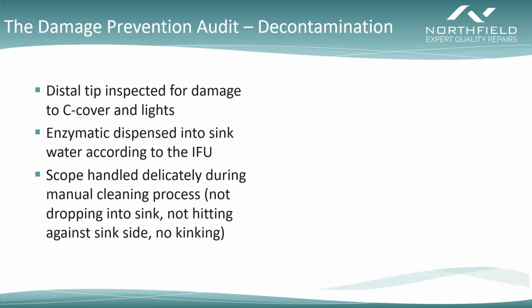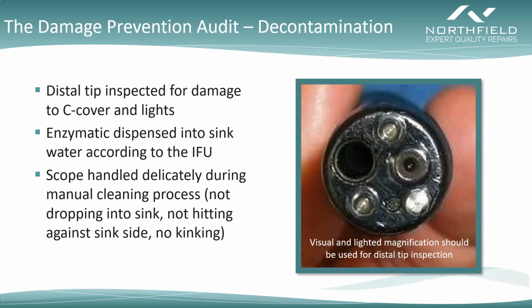But this really highlights the importance of auditing and visual observation, because while I think every technician would say, of course I don't drop my scope into the sink, of course we don't hit it against the sink side, most of the time when these things are happening, it's when you're in a hurry and it's very accidental and you're so focused on maybe what the next step is that you just don't notice that you hit it against the sink side, or maybe you put it into the sink a little aggressively. And so these are things that don't come up unless you have somebody from a neutral standpoint just observing. And it's also very important that you use visual and lighted magnification, especially when you're looking at that distal tip. We're talking about openings and damage that is so small and so subtle that it simply cannot be observed by the naked eye.